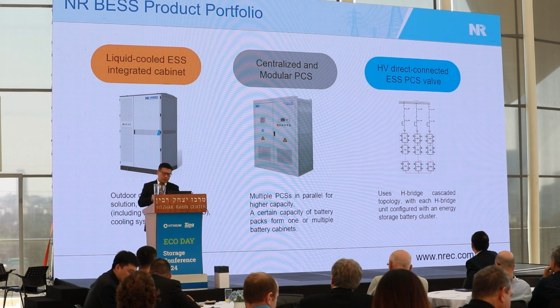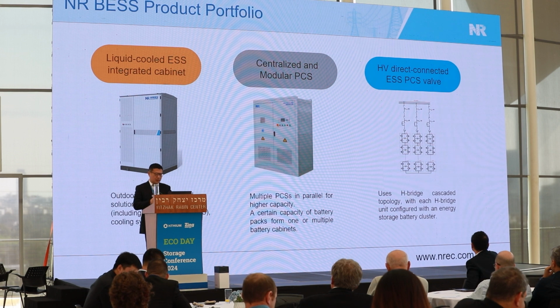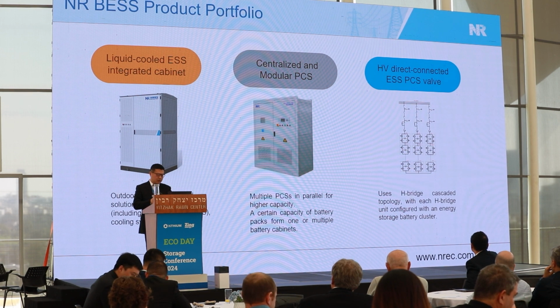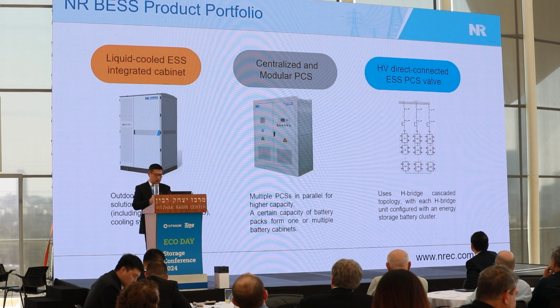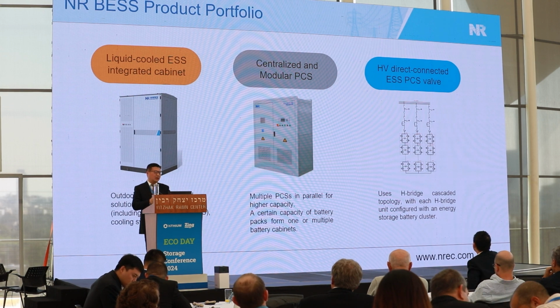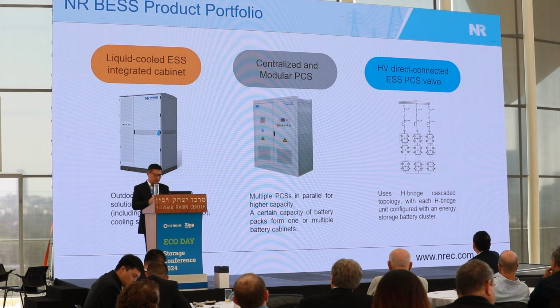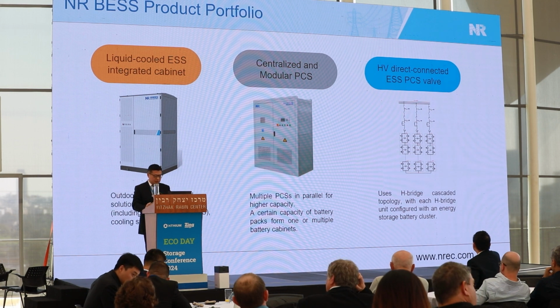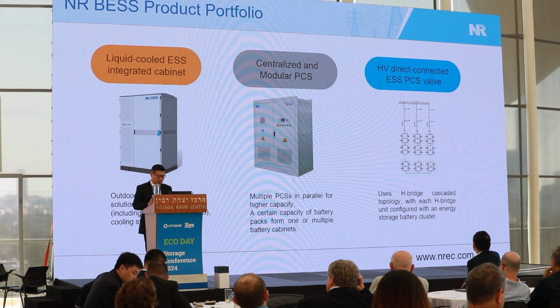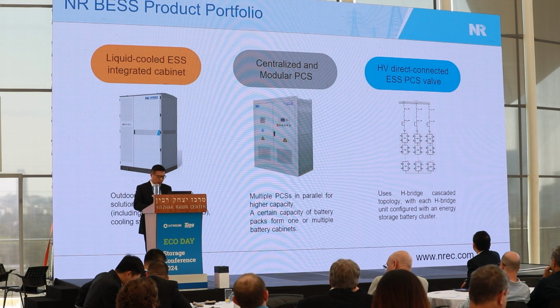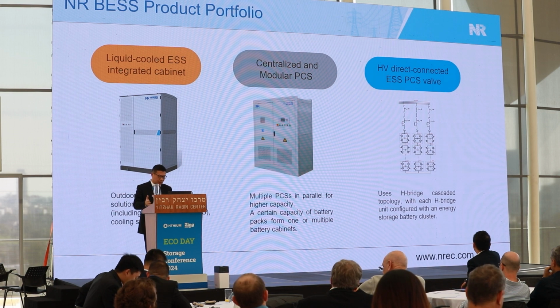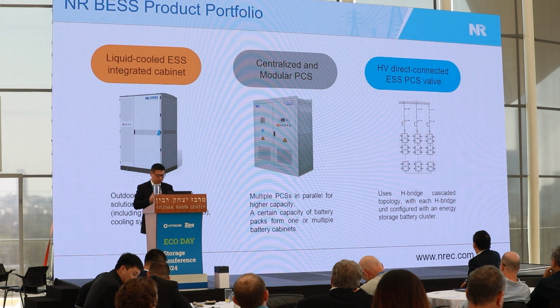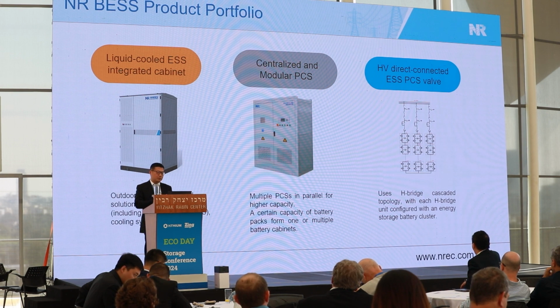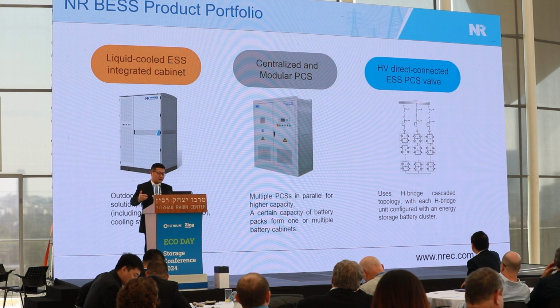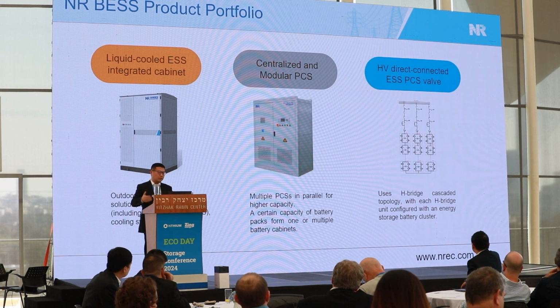Also, based on power electronic experience, we have developed HV directly connected battery storage. It's something like the STATCOM approach, meaning they don't need a transformer. They just use more H-bridge cascaded topology of IGBTs to directly integrate the battery into the system, connecting directly to the HV side without a transformer.